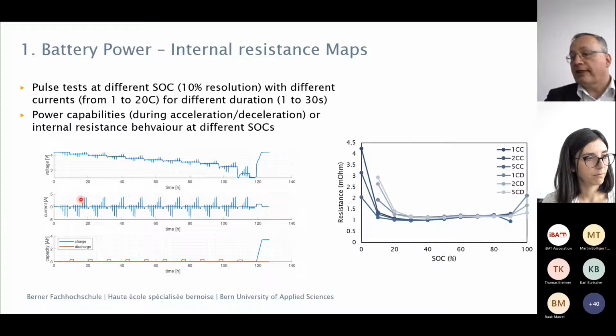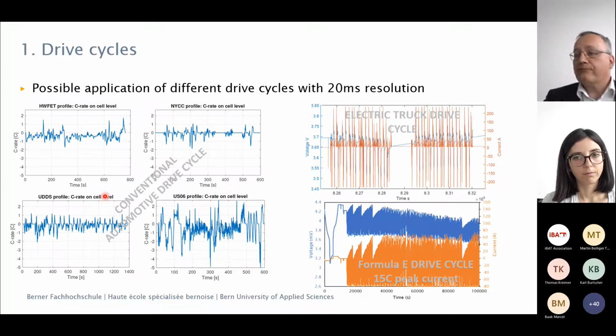You have to slightly increase the pulse each time to see if you're still within the possibilities of the battery. As soon as, for example, for discharge, the battery hits the lower value of the end of discharge voltage at the end of a 30-second pulse, you have to stop. So it's a little bit trial and error.